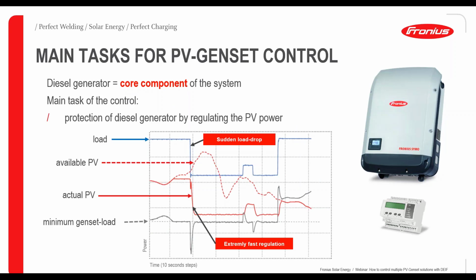Quickly want to again tell you about the core components and the use in the scenario. So the main task for a PV-Genset control, the reason why we need it, is actually to protect the diesel generator itself, because this is the core component, as we previously mentioned. And to protect it, it has to be controlled. The inverter has to be controlled, and this is done by regulating the PV power.